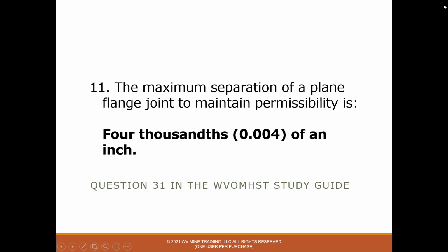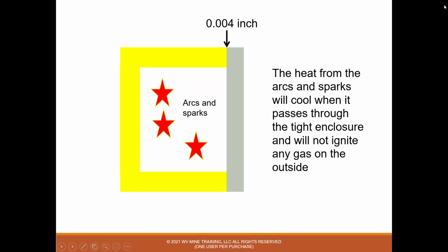11, the maximum separation of a plain flange joint to maintain permissibility is, and that's 0.004 of an inch. And here's a little picture. So here I have an enclosure, and this is a plain flange where the lid just bolts onto the enclosure, and 0.004 of an inch is the biggest gap that you can have here. And the purpose for that is you could have arcs and sparks within this enclosure. There's a lot of electrical connections being made in there, and it could arc and spark, and you could actually have an explosion in there.